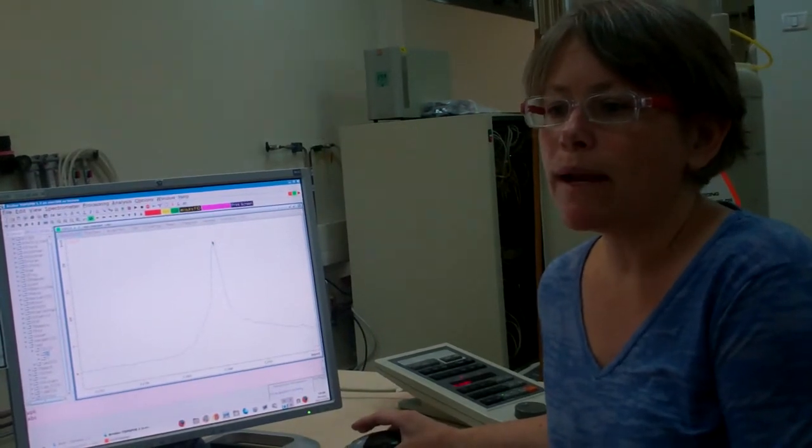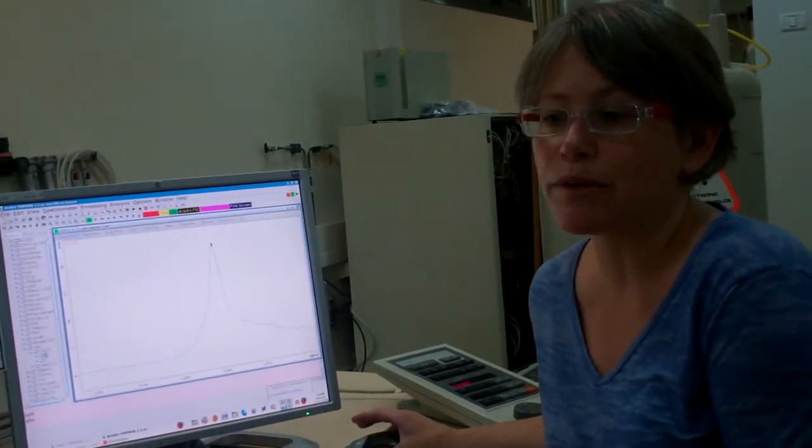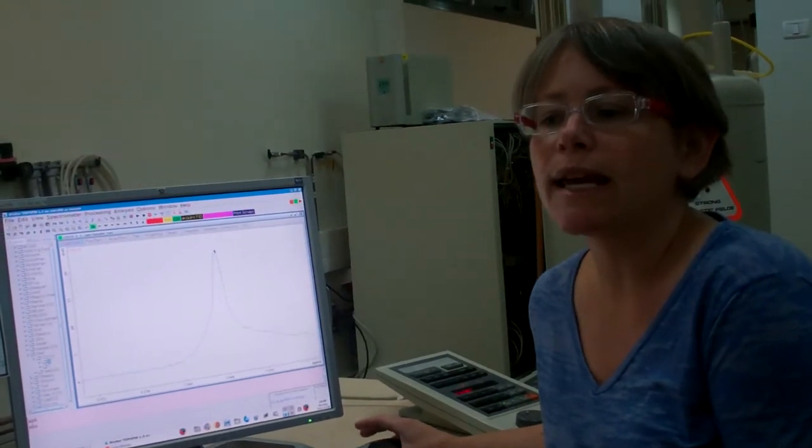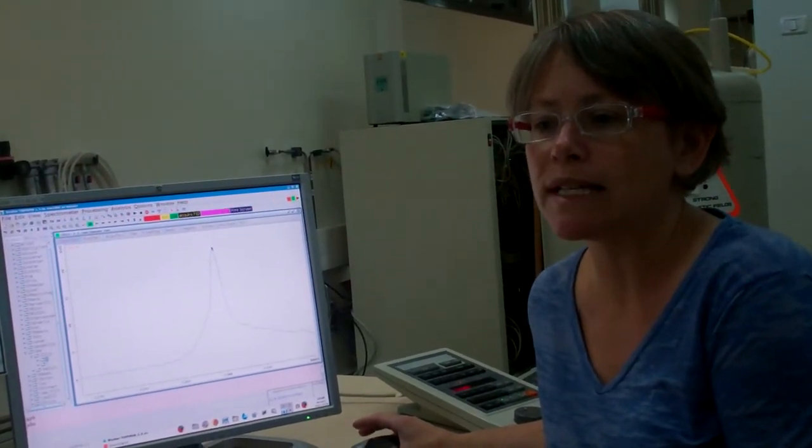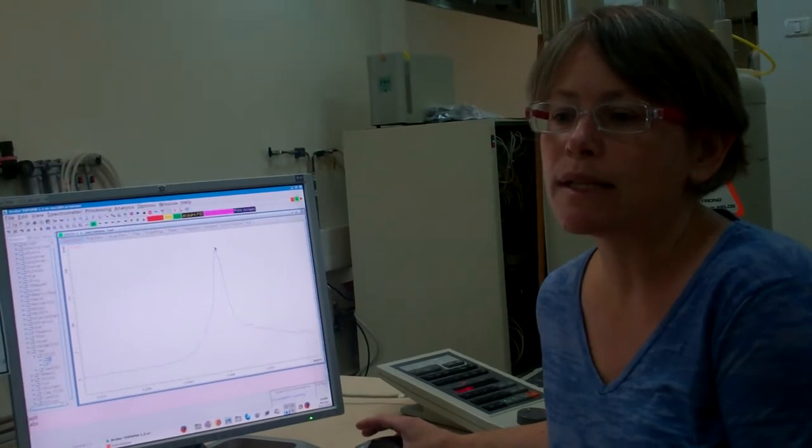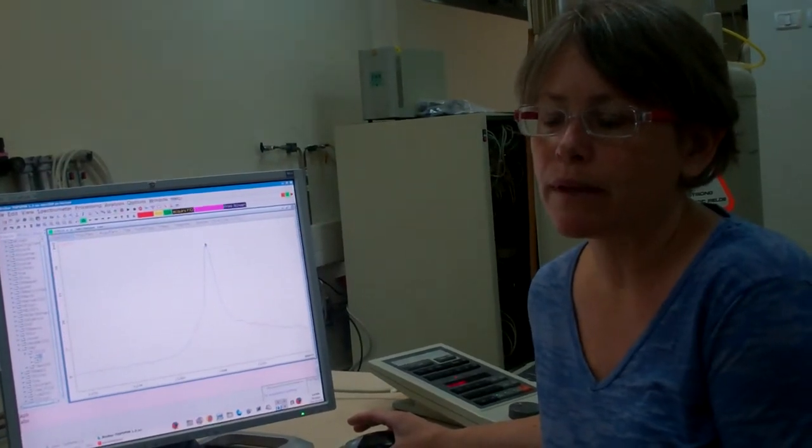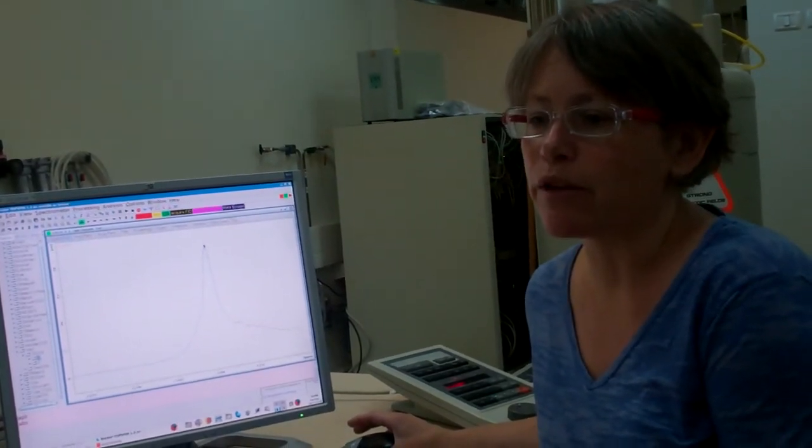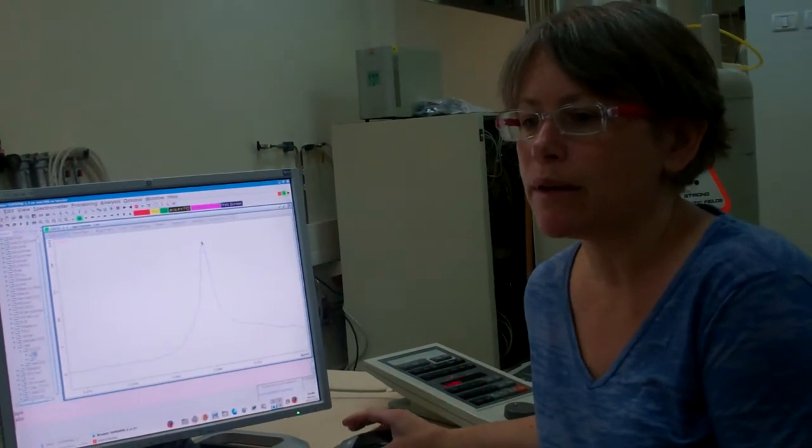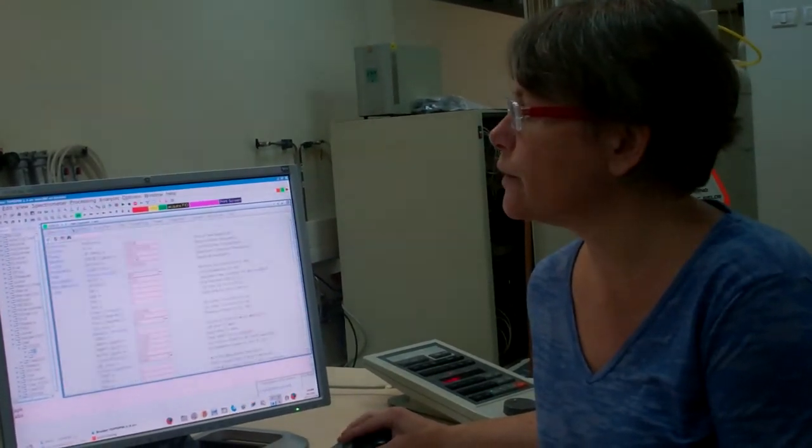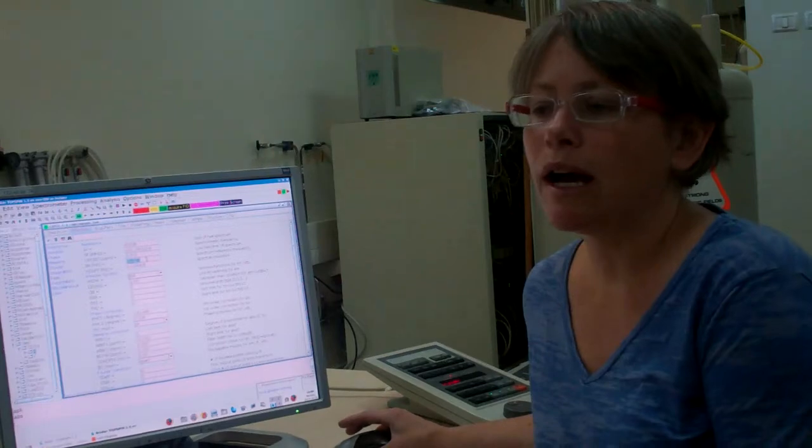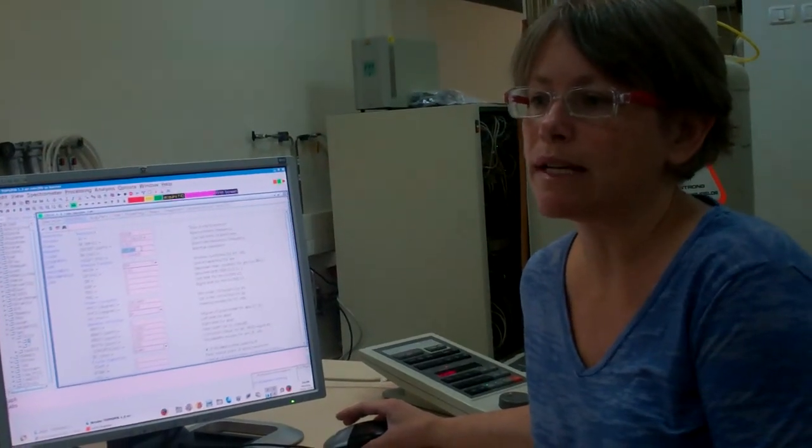When I write up the experimental section of my thesis, my poster, and my article, I will write that I calibrated the residual proton signal of the deuterated chloroform to 7.26 ppm. Let's check back on our SR value in the processing parameters tab. That's where the calibration is stored. Here's our new value, 152.4 instead of 0.